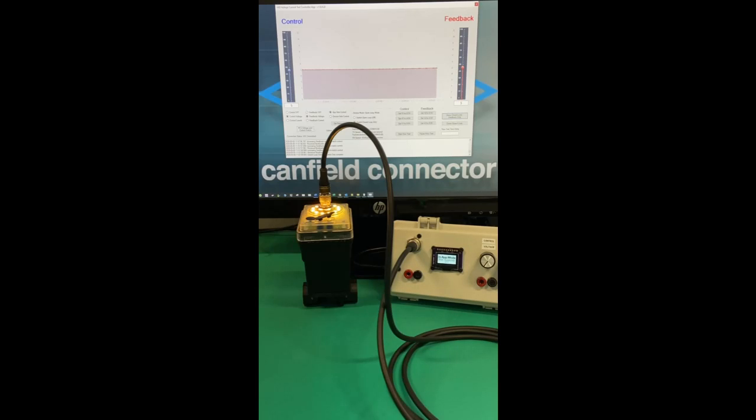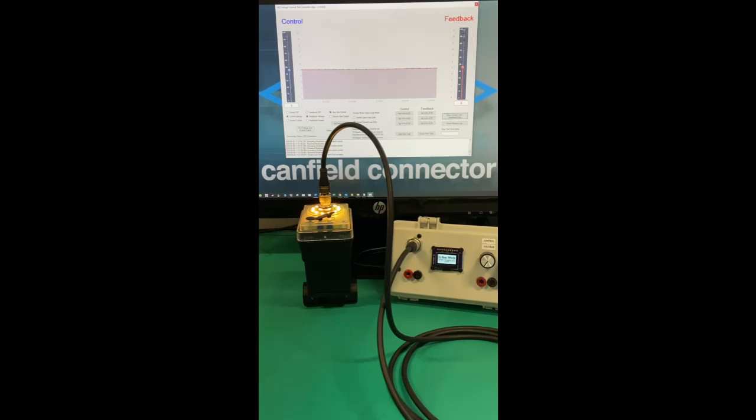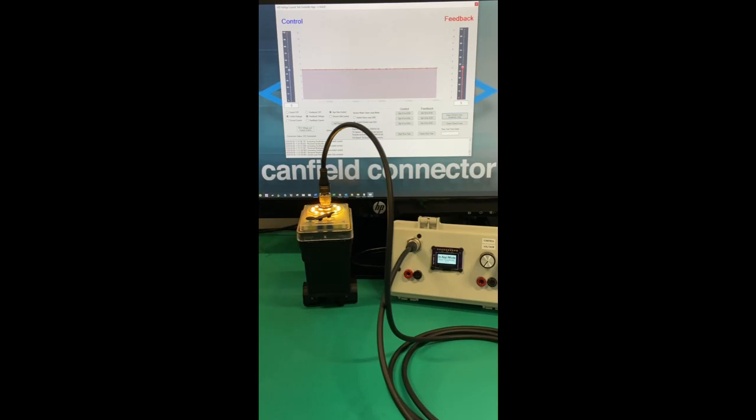A larger setting of the dither pot will mean that the stepper will not react unless there is a larger difference between the two inputs. The dither pot has a minimum setting of approximately 0.1 volts and a maximum of 1.0 volts. When the dither is set to its minimum value, this means if the control and feedback are more than 0.1 volts in difference from one another, the valve will begin to react.